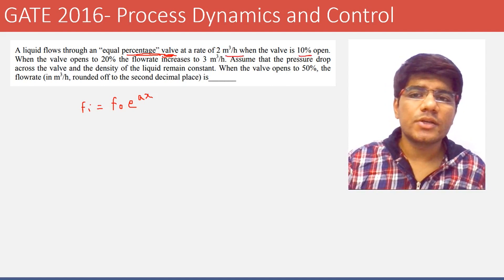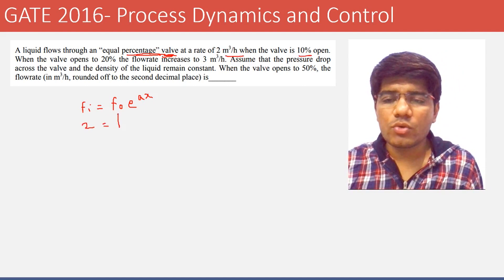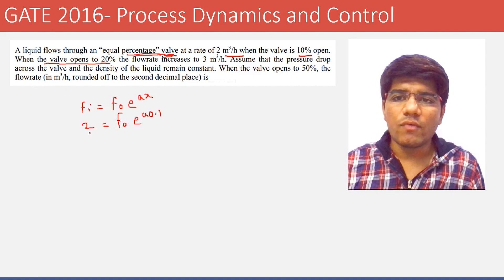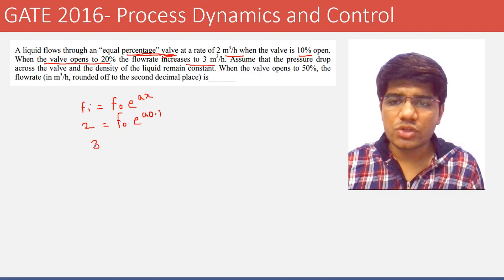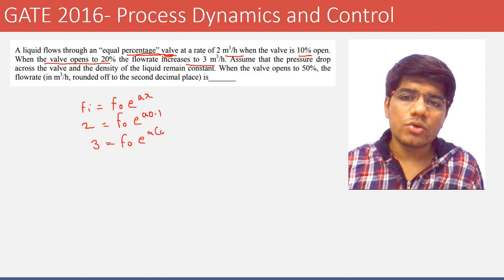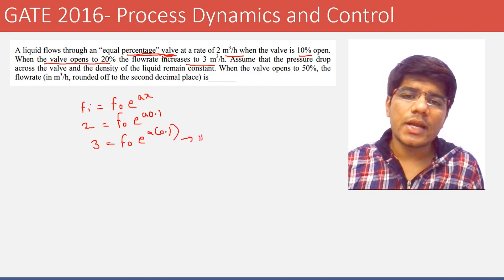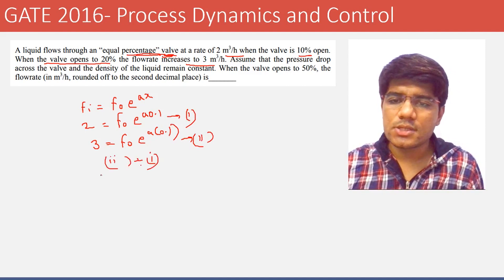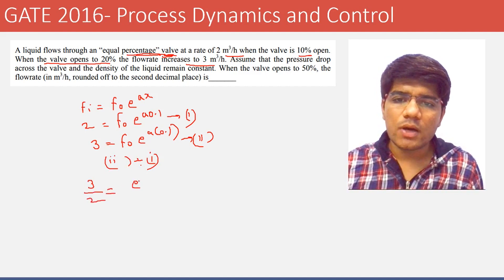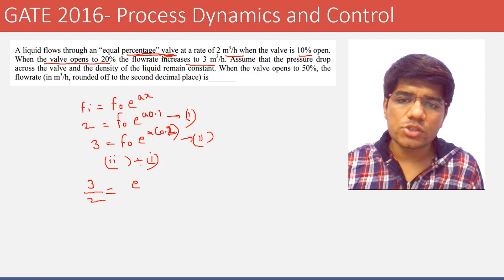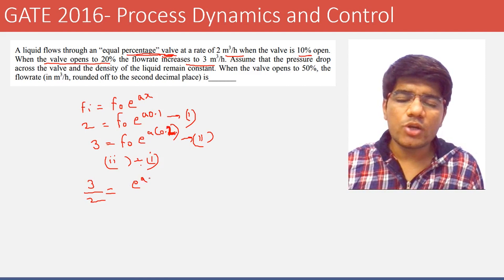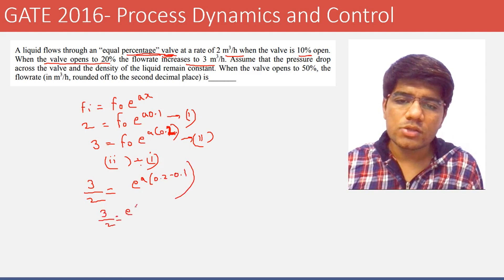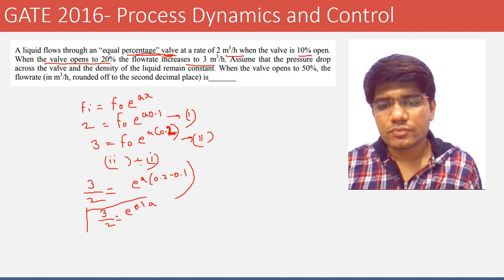The flow rate is 2 m³/hr when the valve is 10% open, so 2 = F₀ · e^(0.1a). When the valve opens to 20%, the flow rate increases to 3 m³/hr, so 3 = F₀ · e^(0.2a). Dividing the second equation by the first gives 3/2 = e^(0.1a).